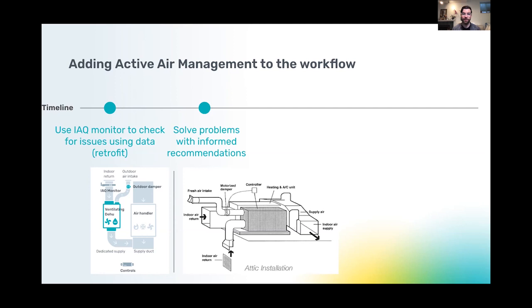And the ventilating dehumidifier, we're typically running it frequently, and it's got a filter inside of it. And some of them have even a MERV 13 filter. And so you're getting additional filtration, both of the outdoor air, but also of the dedicated return air running through that piece of equipment. So it's a good all-around solution where it addresses all three pillars effectively. And it usually works if you know a few of the installation nuances that can cause issues.